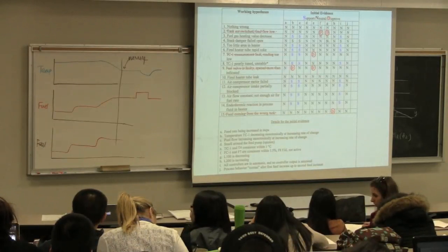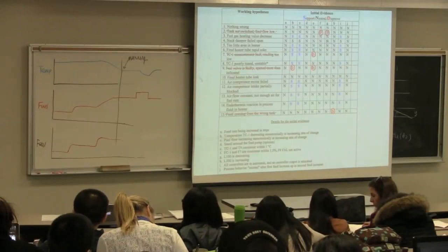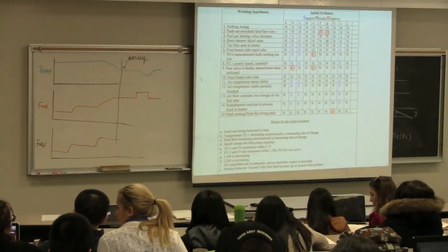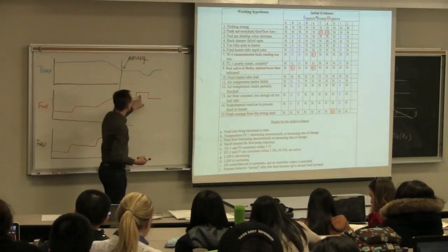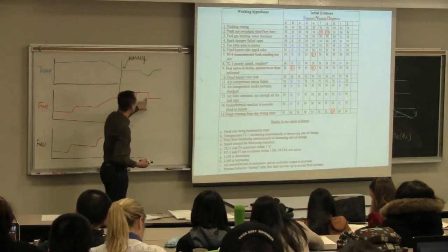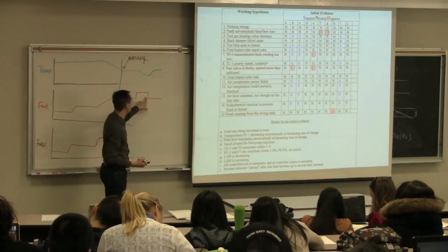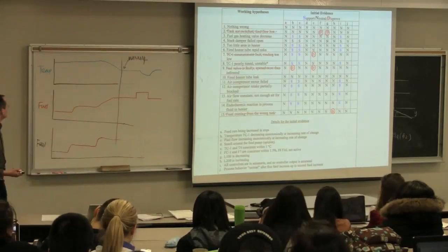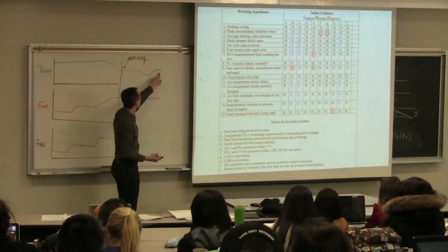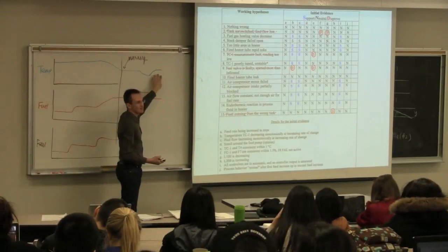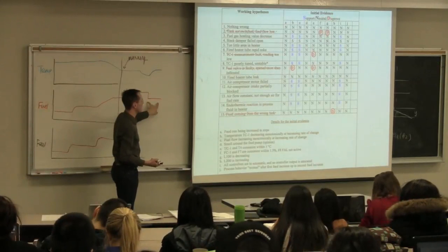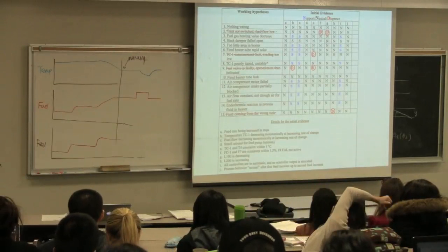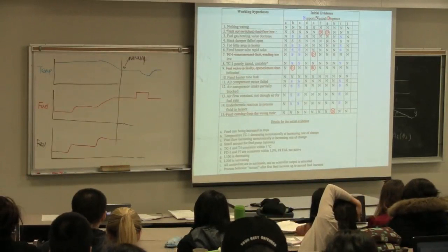If I had the ability to measure carbon monoxide and carbon dioxide at the top, I would see my carbon monoxide increase because I've got incomplete combustion. And then when I come back down again, this further emphasizes it to me: when I decrease my fuel flow and I see an increase in my temperature, that's a perfect indication of that situation. Because now I'm putting less cold fuel in, I'm able to get to the higher temperature that I need.